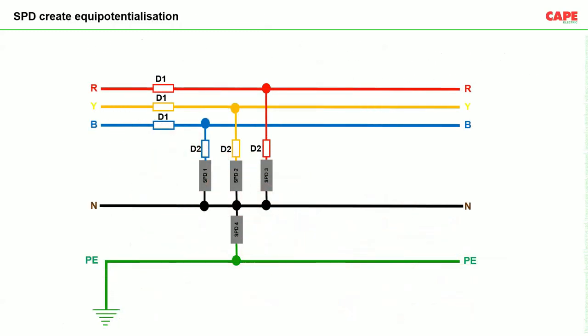Now, an important point is, how do we connect an SPD in an electrical system? Suppose we have an electrical system, three phase R, Y, B, neutral and protective earth. Now there are two methods of connecting an SPD, a 3 plus 1 connection and a 4 plus 0 connection. For the sake of explaining, we have taken a 3 plus 1 connection. In this connection, you can see that three SPDs are connected between line and neutral, and the fourth SPD is connected between neutral and earth. Similarly, another possible configuration is that all three lines and neutral can be directly connected to earth. Right now, we are going to discuss this particular configuration.